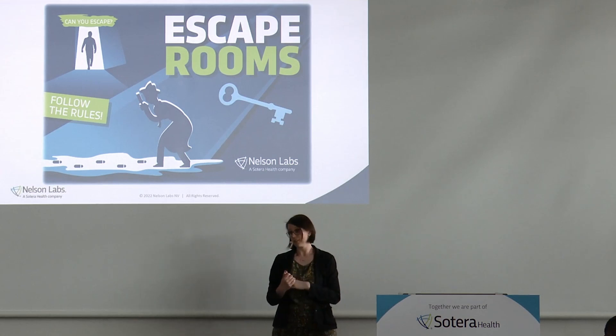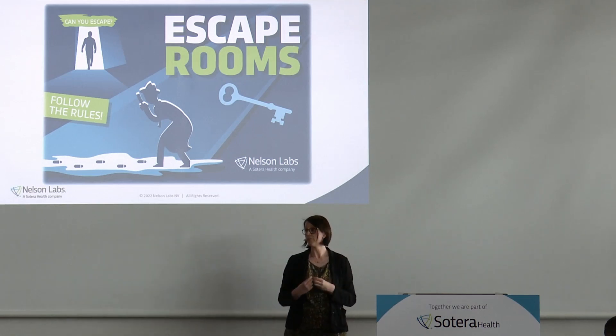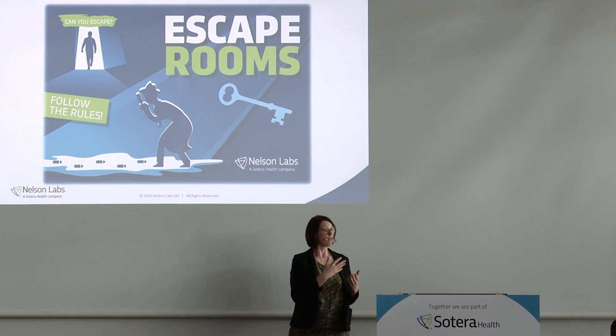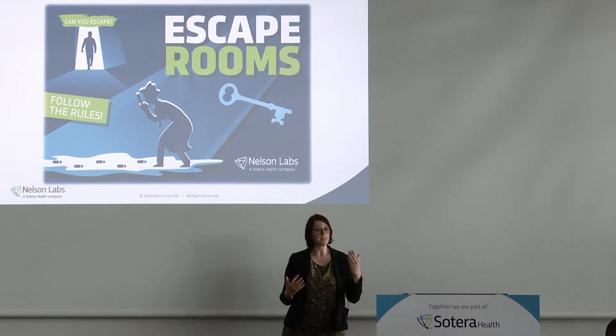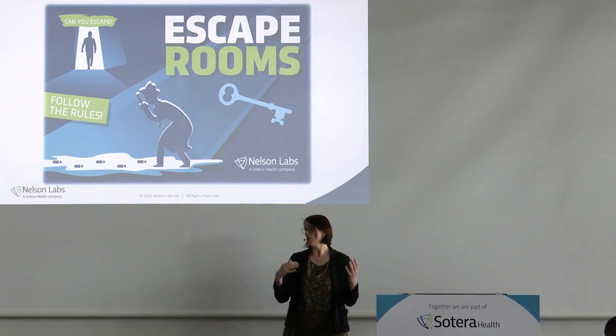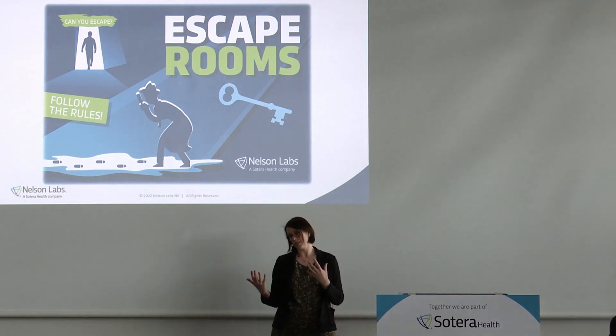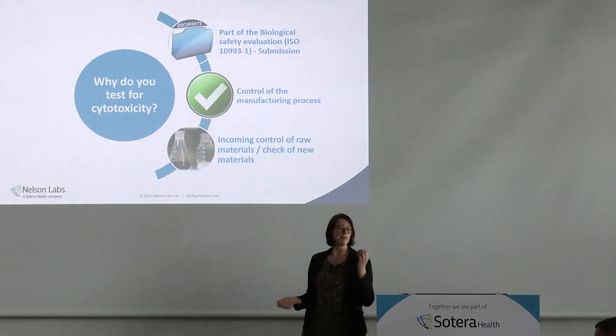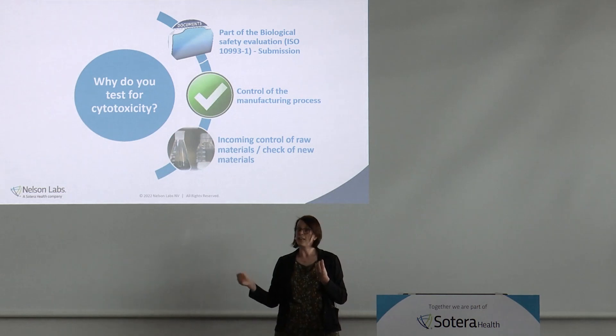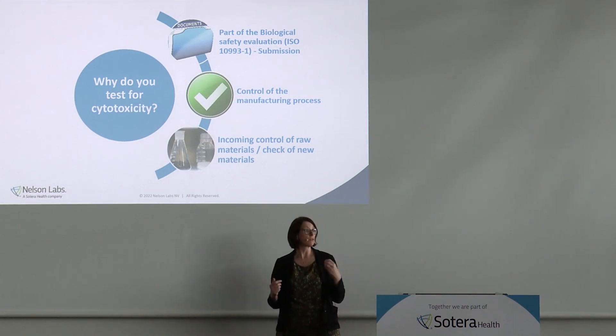The second word is cytotoxicity — it's very important. Why are we performing a cytotoxicity test? For each medical device, you have to demonstrate its biocompatibility, that it's safe for use. Through ISO 10993-1, biological safety evaluation through a risk assessment, one of the endpoints is the cytotoxicity test, where you demonstrate whether your device has a potential cytotoxic effect on cells. It's an important part, it's cheap and fast, so everybody does it — for your submission, as a quality control check in manufacturing, or to select raw materials.